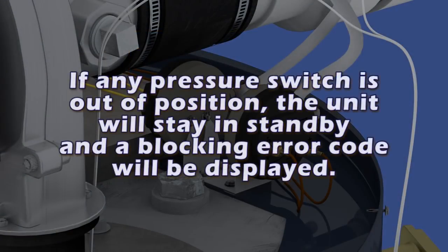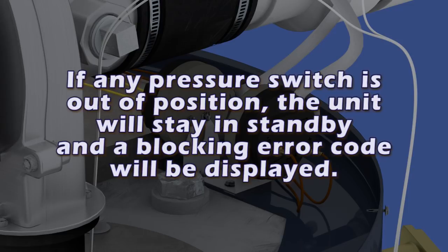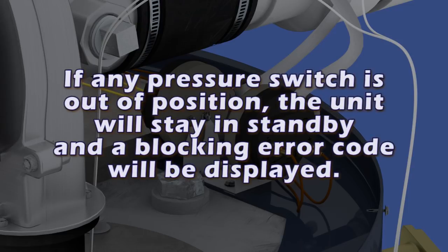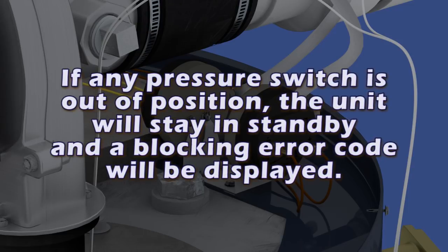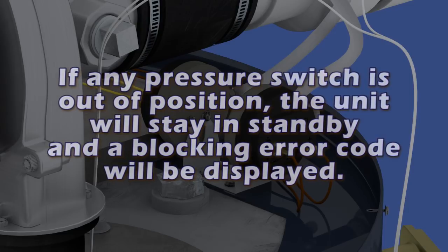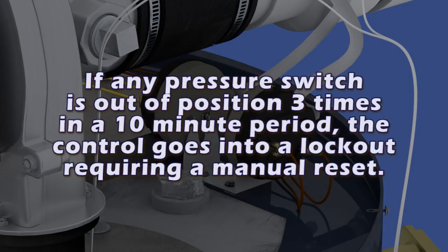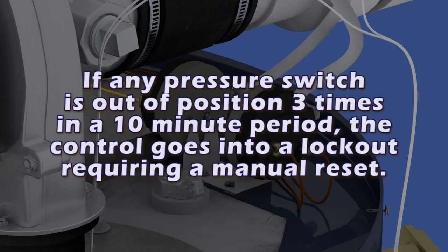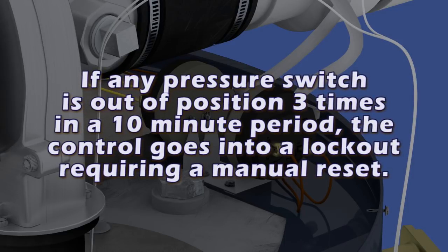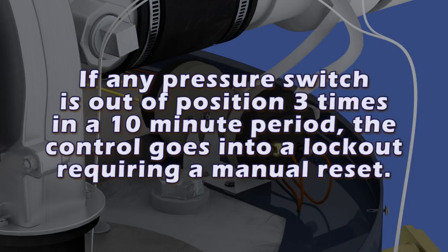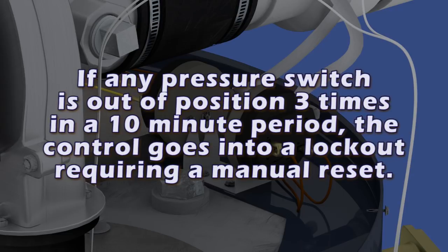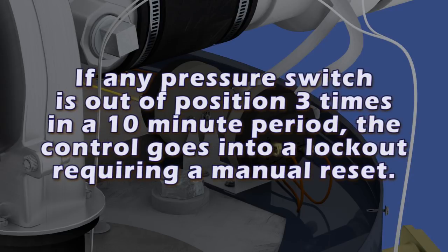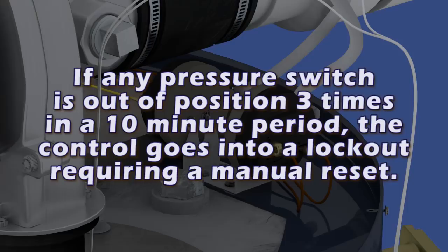As a general rule, if any pressure switch is out of position, the unit will stay in standby and a blocking error code will be displayed until the error is cleared. If any pressure switch is out of position 3 times, either running or standby within a 10-minute period of time, the control goes to a lockout, requiring a manual reset, and a lockout error code will be displayed.